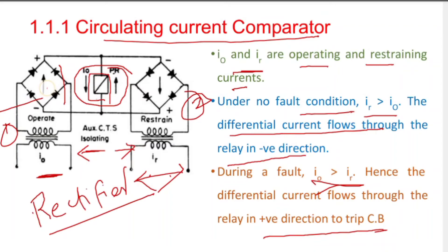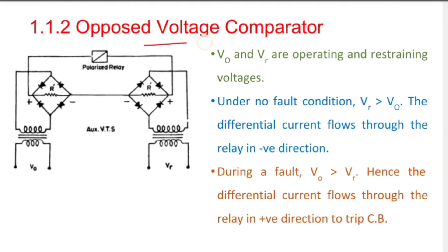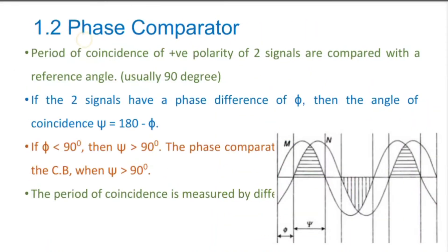For more accurate results, the bridge rectifier can be replaced by a precision rectifier employing operational amplifiers. In the opposed voltage type comparator, V0 and Vr are the operating and restraining voltages. V0 is given for one VT and Vr for another. When Vr is greater than V0, the differential current flows in the negative direction; if fault occurs and operating quantity exceeds restraining quantity, the differential current flows in the positive direction to trip the circuit breaker.